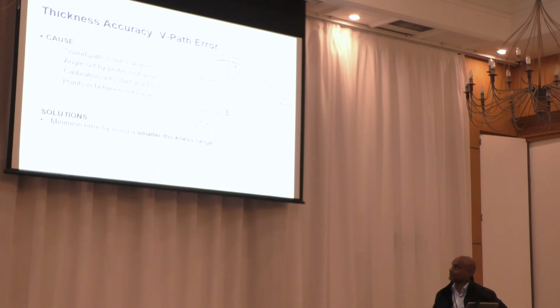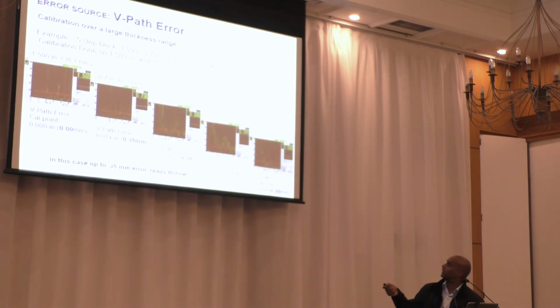So when you come into a situation like that, the best approach is knowing the current material and what the thickness range should be, from new to what your tolerances are, then going back in here and maybe using 1, 2, 3. So using the 3/4 and 0.15 inch as your two calibration points, instead of having such a wide range, to get your accuracy levels higher and your errors lower.